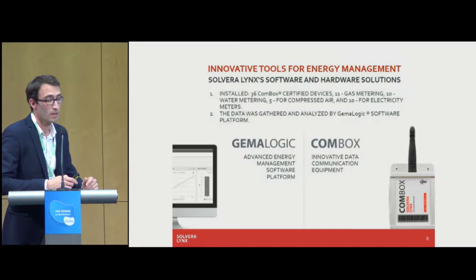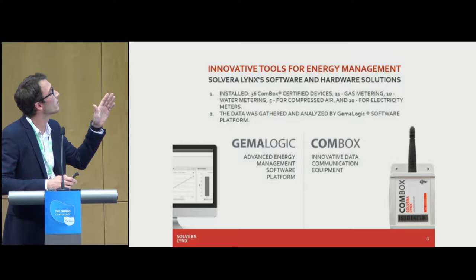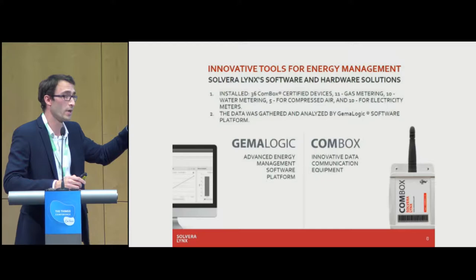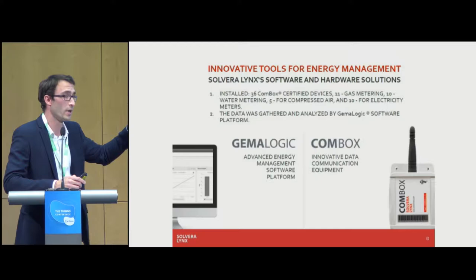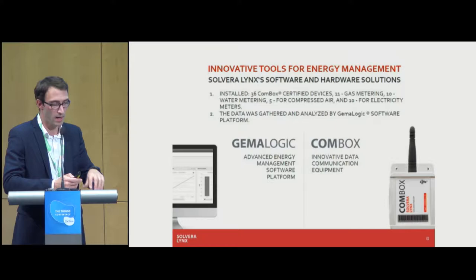We installed altogether 36 ComBox devices certified with LoRaWAN: 11 gas meters, 10 water meters, 5 for compressed air meters, and 10 electricity meters. All data was gathered from our ComBox device, which is connected to the network server sending the data payload directly to the network management server and from there to GemaLogic. The workflow is quite easy: we collect data from the meter, wire the meter with two wires, and connect our ComBox device.